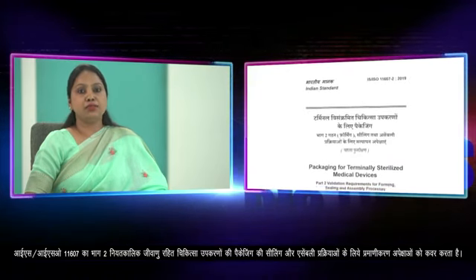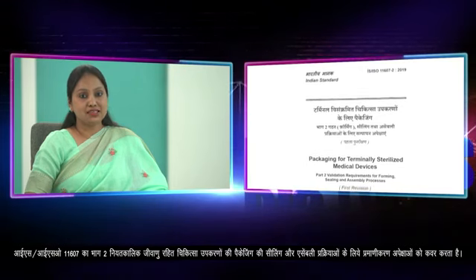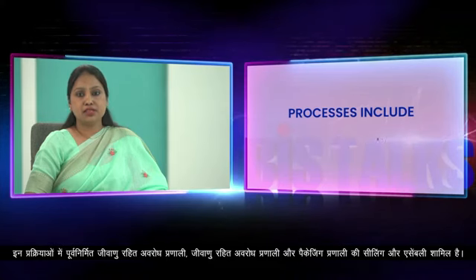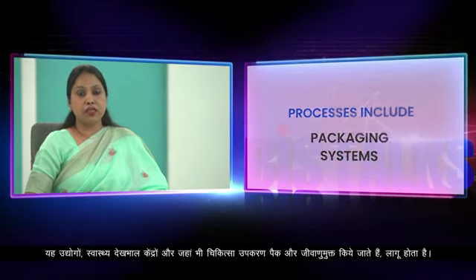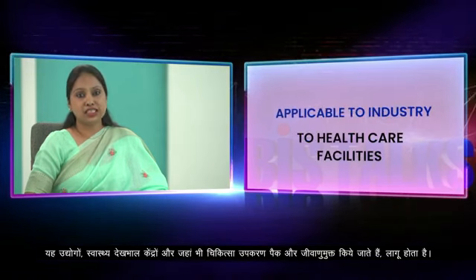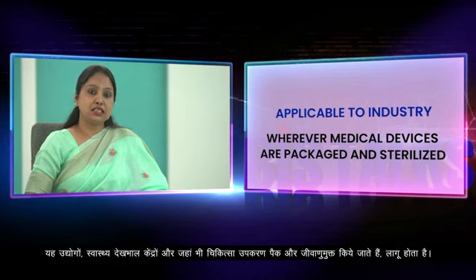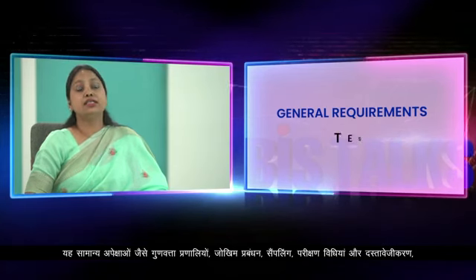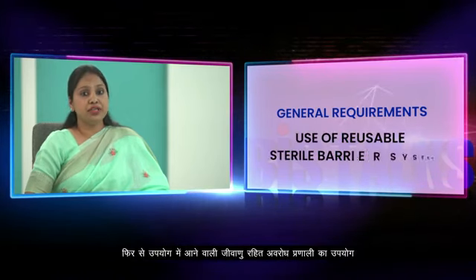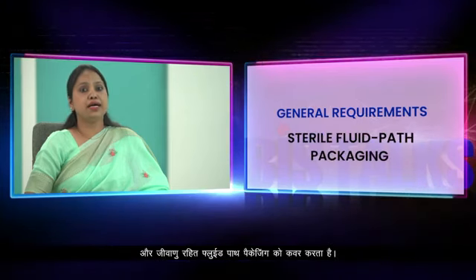The Part 2 of ISO 11607 covers the validation requirements for forming, sealing, and assembly processes for packaging of medical devices that are terminally sterilized. These processes include forming, sealing, and assembly of preformed sterile barrier systems, and packaging systems. It is applicable to industry, to healthcare facilities, and to wherever medical devices are packaged and sterilized. It covers the general requirements like quality systems, risk management, sampling, test methods, documentation, validation of packaging processes, assembly, use of reusable sterile barrier systems, and sterile fluid path packaging.